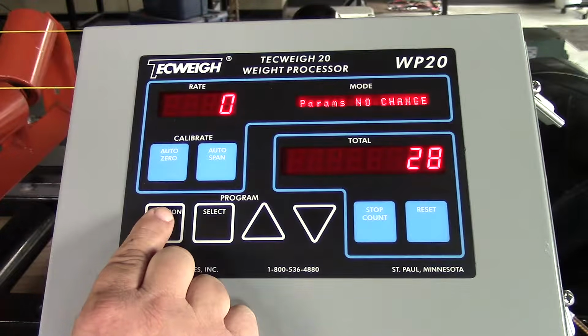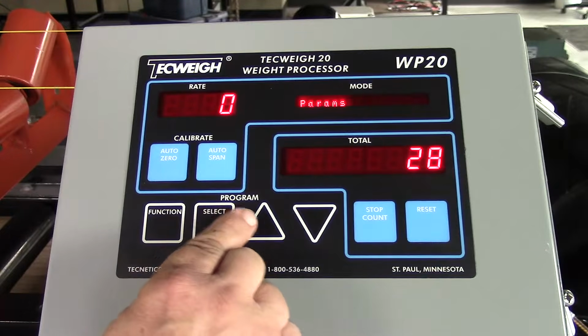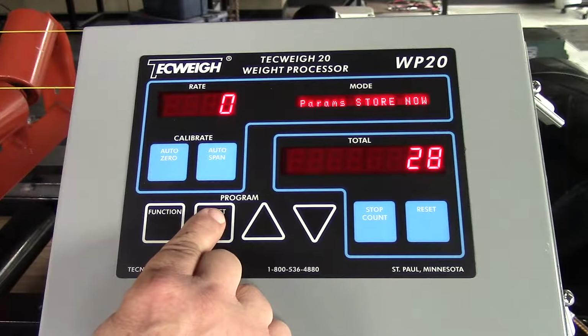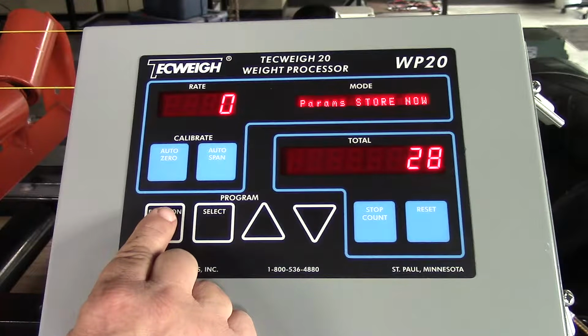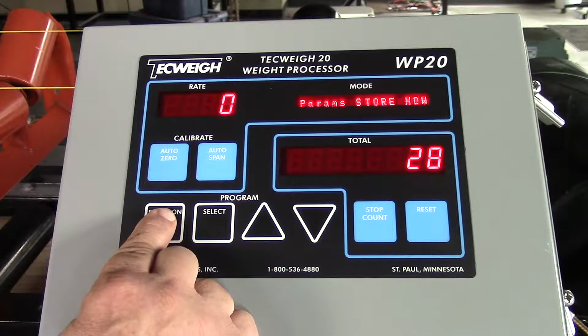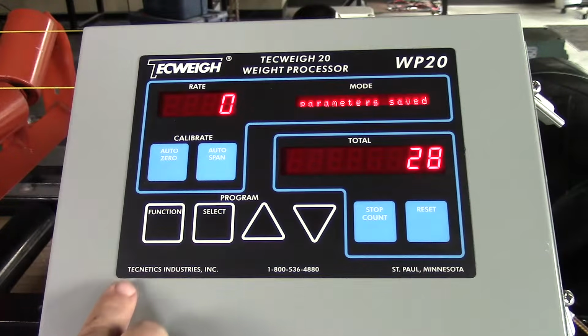A really good practice to do is after calibration and everything is all done, to go into params and select store now, then go out into the operating mode by holding down the function key for 5 seconds and save a backup copy of all the parameters. It's just a really good practice to do. And there you have it. The unit's all programmed and ready to calibrate.